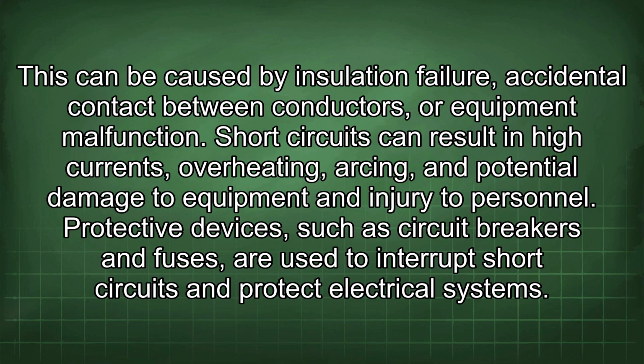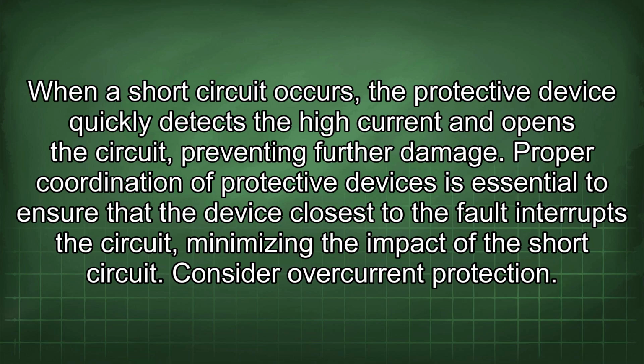Protective devices, such as circuit breakers and fuses, are used to interrupt short circuits and protect electrical systems. When a short circuit occurs, the protective device quickly detects the high current and opens the circuit, preventing further damage. Proper coordination of protective devices is essential to ensure that the device closest to the fault interrupts the circuit, minimizing the impact of the short circuit.